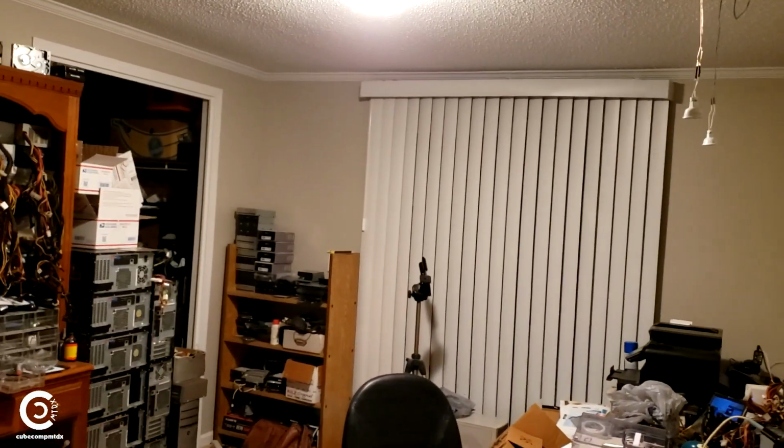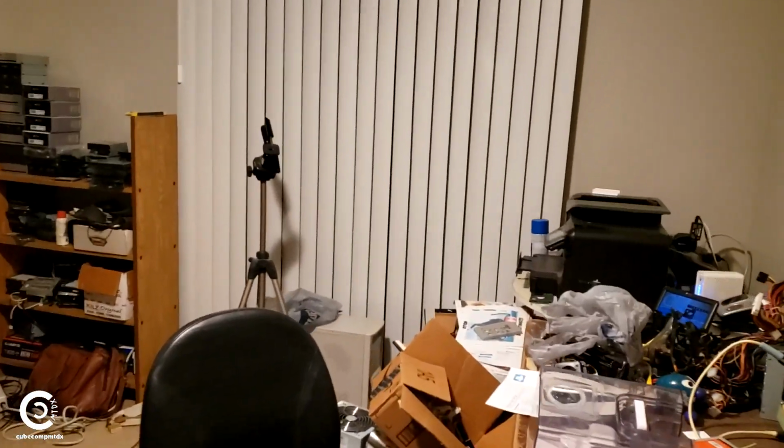This thing will probably bring on the auxiliary heat, because it's simply not enough heat out there. Well, the thing is, when it's that cold outside, heat pumps just cannot keep up on their own. Plus, we got this super cool air in the rooms of the house, so start circulating that air like that, it's going to actually bring more of that cool air into the thermostat, and the thermostat's going to be like, oh, we need to bring on the second stage.